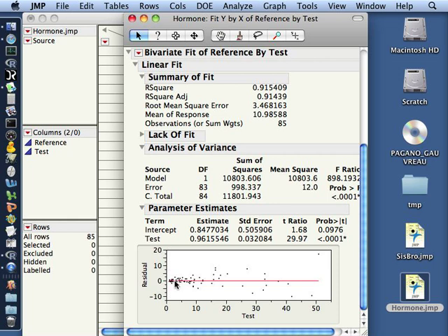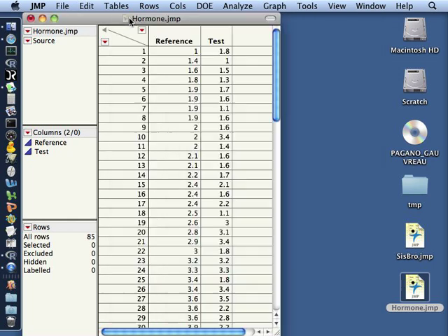We're very close to the predicted value, the reference value. For very high values of the test assay we're somewhat farther away from the reference value. So the residuals are higher for high values of test than they are for lower. So let's do some transformations and see if we can correct this problem.